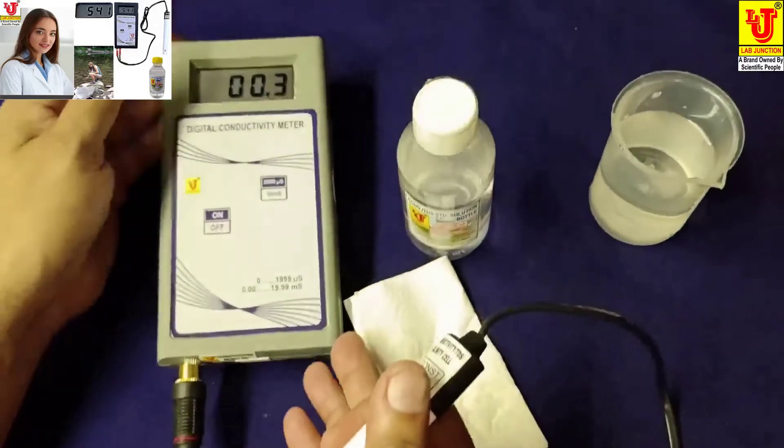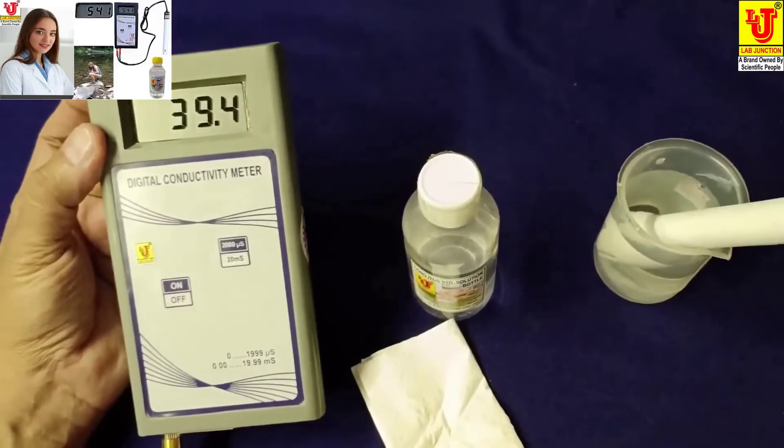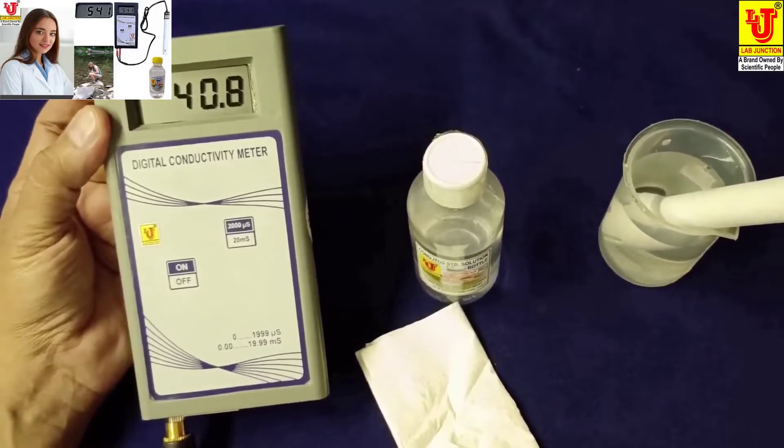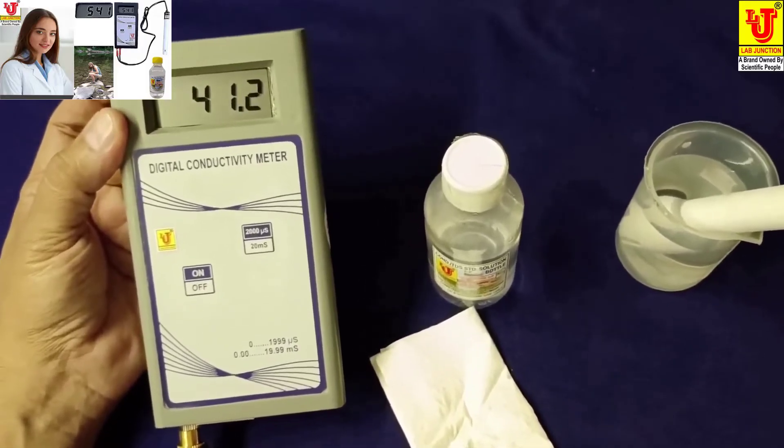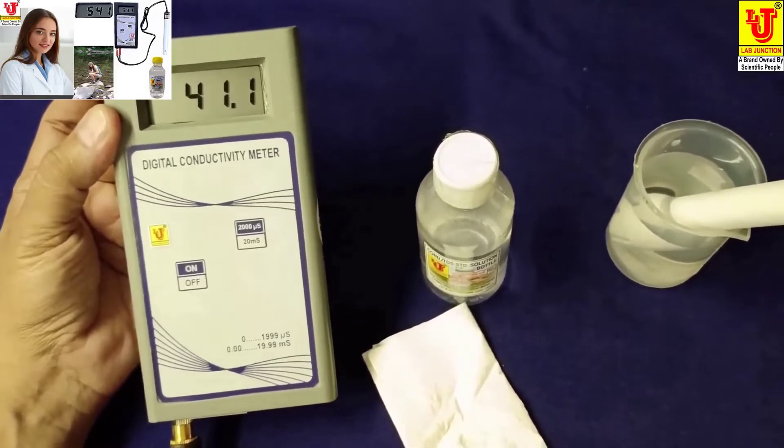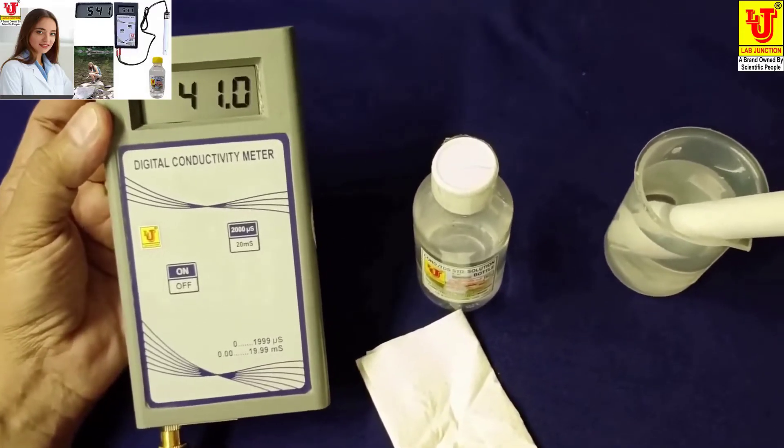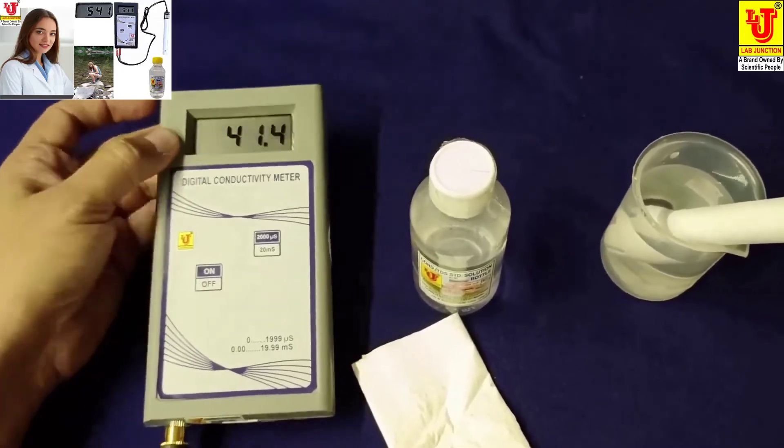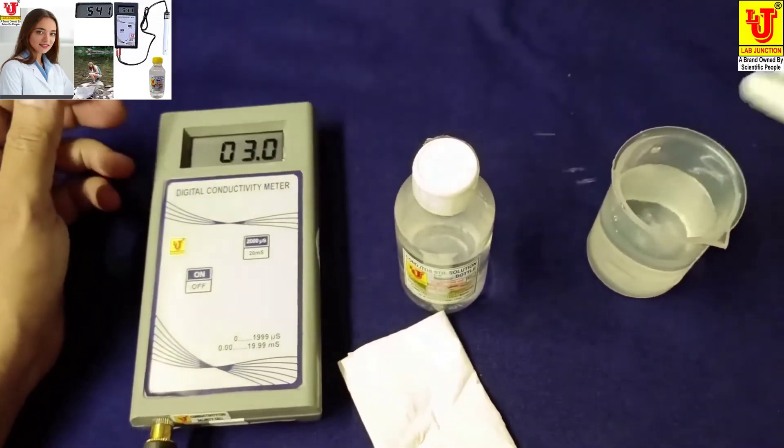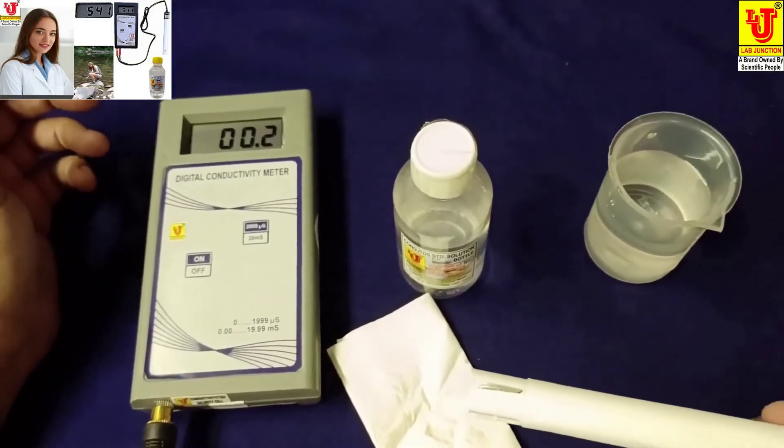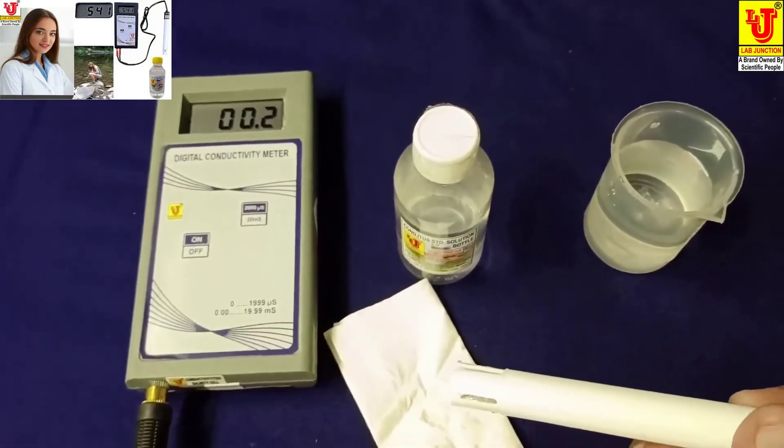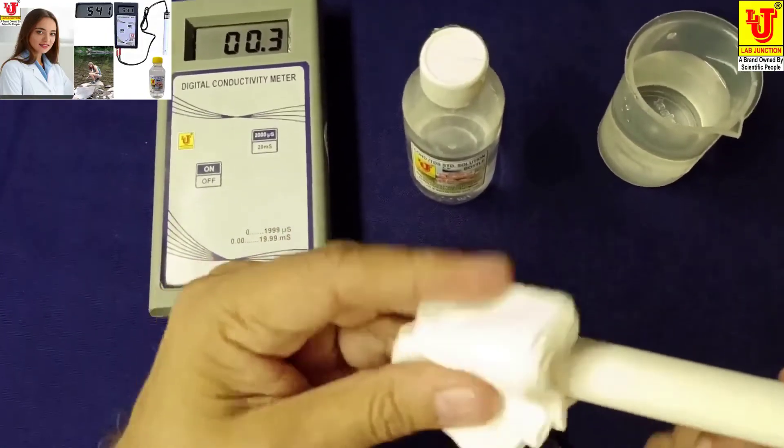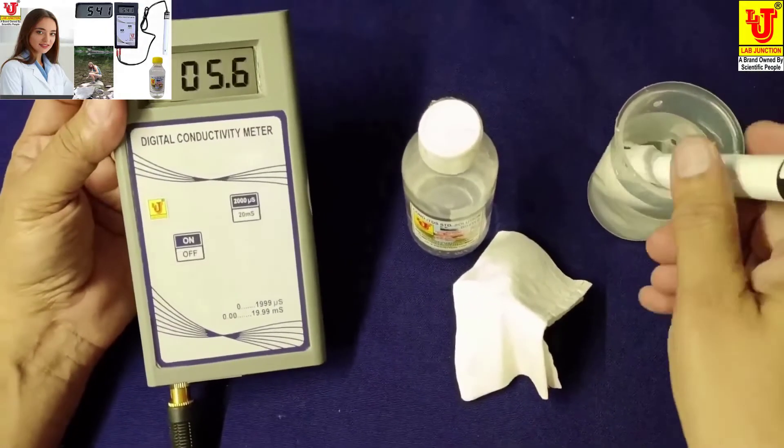And directly dip in another sample. For better precautions first you have to wash conductivity cell with distilled water, then refresh with tissue paper and dip in another sample. For better results please take this precaution to maintain better results.